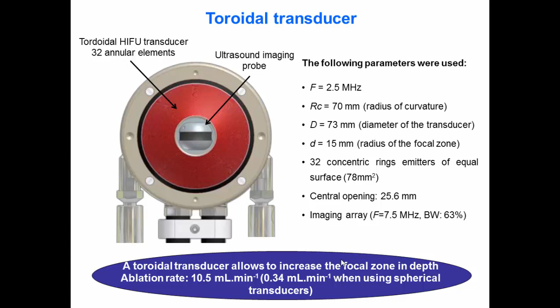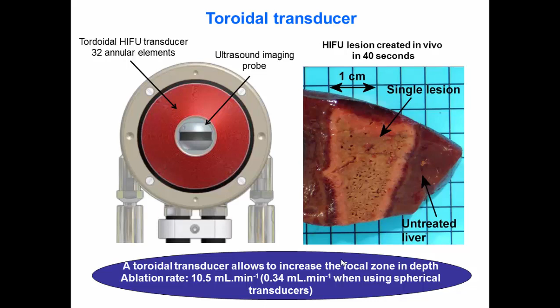There is a central opening in the center of the HIFU transducer to place an ultrasound imaging array working at 7.5 megahertz. We demonstrated in vivo in pig livers that the ablation volume can be significantly increased. This is a lesion that has been obtained in only 40 seconds of treatment, significantly increased when compared with a conventional spherical transducer. The ablation rate using the toroidal transducer is about 10.5 cubic centimeters per minute versus 0.3 cubic centimeters with equivalent spherical transducers.